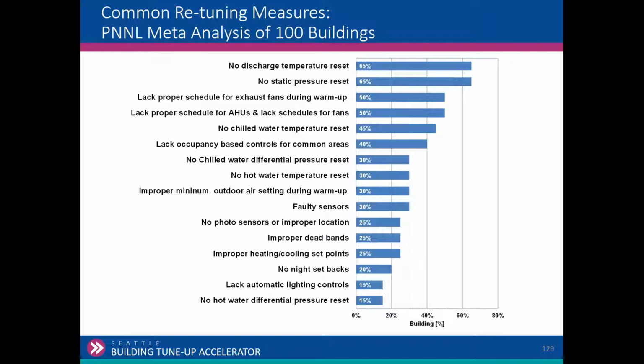Lack of occupancy-based controls for common areas. We'll talk about that. Chilled water reset, hot water, no hot water temperature reset. Faulty sensors, a relatively small percentage, but at a minimum you want to verify the accuracy of your critical sensors, those sensors that initiate control action, like discharge air temperature, outside air temperature, mixed air temperature if you've got a mixed air economizer. Zone temperature sensors, I wouldn't worry about them. They don't fail that often. CO2, probably check that, especially duct-mounted CO2 in the return air. Check those, but zone thermostats, I don't think it's worth the time. So think about the critical sensors that are initiating system-wide control action.